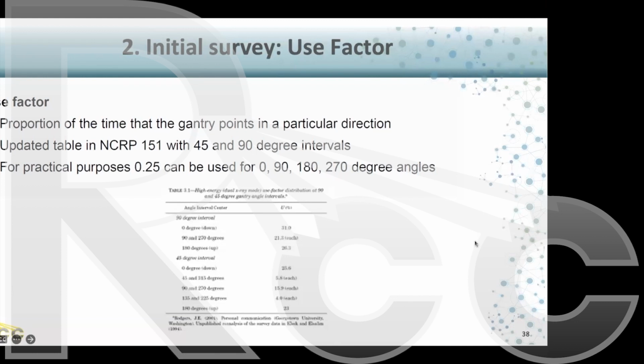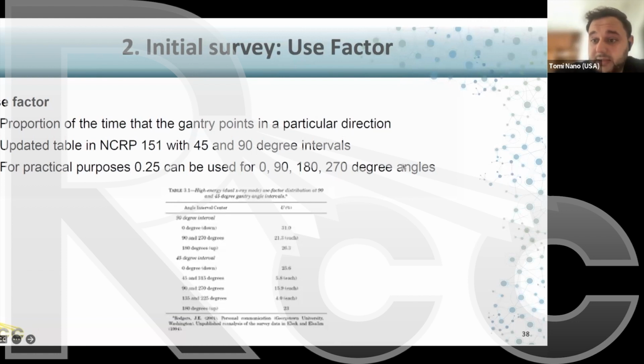Yes. So it depends on the vault design. For example, you can use maybe less shielding, and then you have a safety area, and then you perform your measurements outside of that safety area.